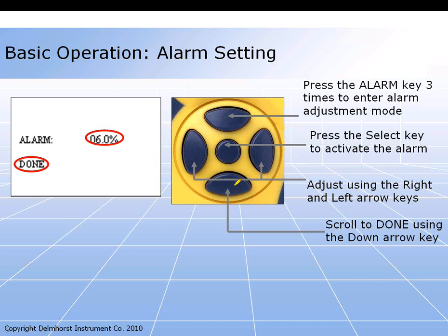How does that factor into the alarm? It gives you a lot of flexibility, because if we're checking in my office, we can set the alarm for 55. It's in 5-point increments, and we know that that's a number that's considered a dry standard in that particular environment. We set the alarm for 55. Anything that reads above 55 is going to beep at you. If we go into the hallway and we set it for 35, anything above 35 is going to beep at you.